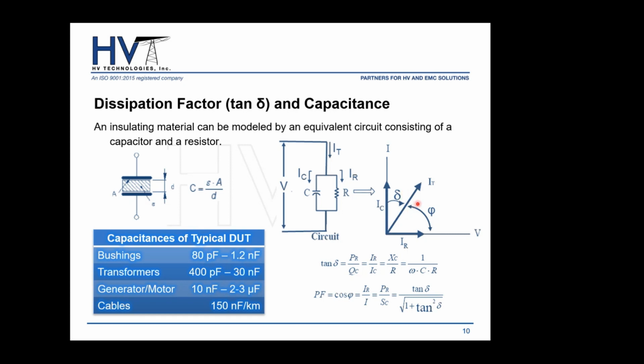Similarly, when we talk about power factor, we're talking about this angle between the resistive current and the total current. So that'll give this angle phi. And so basically tan delta is the ratio between your resistive current, this vector, if we place it over here, it'll be the tangent of this angle, and we will get your resistive current over your capacitive current. That would be tan delta. So we're talking about your resistive power over your reactive power.